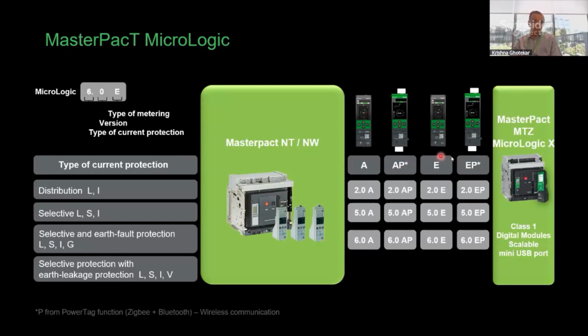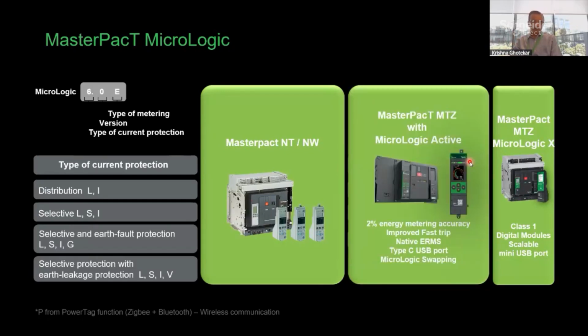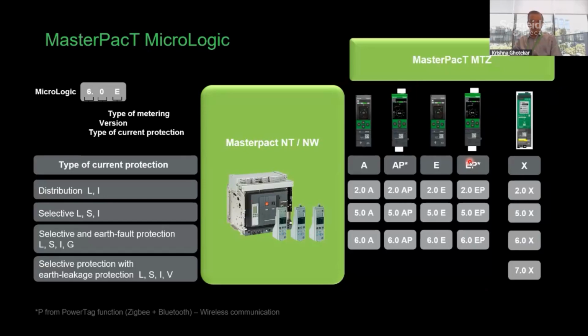On top of that, AP and EP have Bluetooth plus Zigbee connectivity to connect seamlessly with your PAS 600 gateway. So there are four types of trip units: A and E, or if you need wireless connectivity or a communication, just change the trip unit to AP and EP. How to change that, I will show you in the next few slides. So now with MasterPact MTZ, you have a standard type of trip unit, A and E. If you need connectivity, we can have AP and EP wireless connectivity, or you have MasterPact MTZ with MicroLogic X, which is with high-end features like harmonics, under voltage, over voltage, or reverse power kinds of protections.